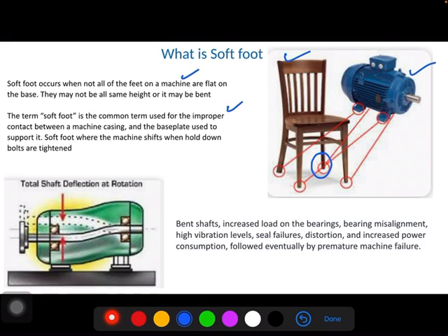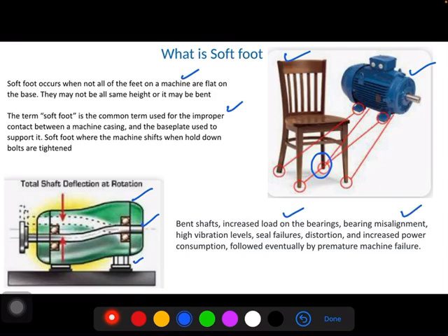When there is a soft foot, you tighten the short leg. It distorts or deforms the machine frame. There will be a bending of the shaft and the center line of the shaft shifts. There will be a misalignment between the drive end and non-drive end bearings. So there will be increased load on the bearings, misalignment, and high vibration levels. There will be seal failures, increased power consumption, and it is followed by premature machine failure.